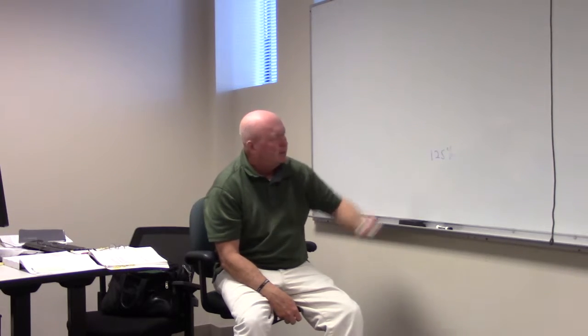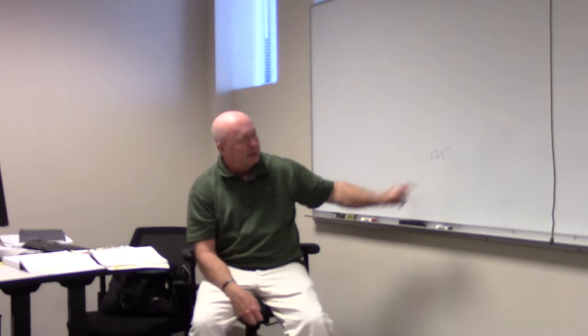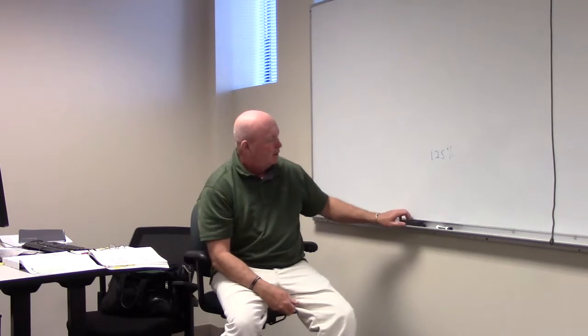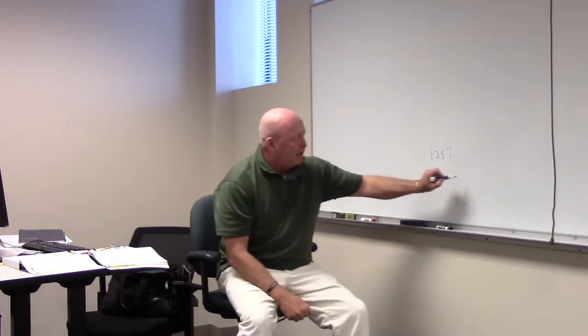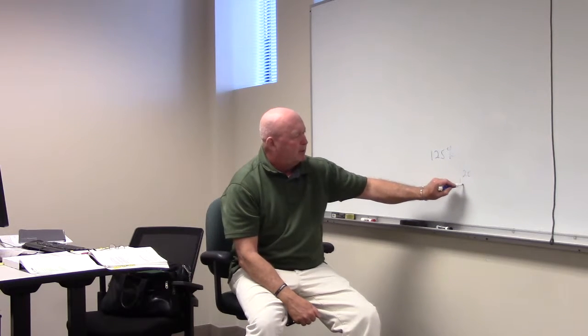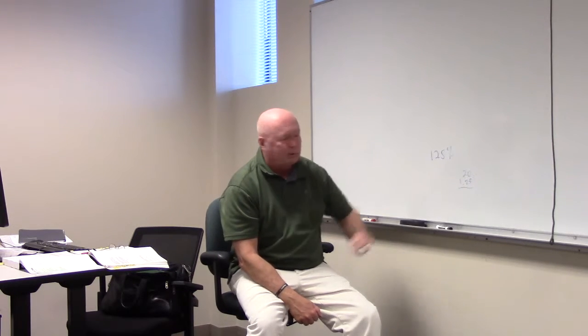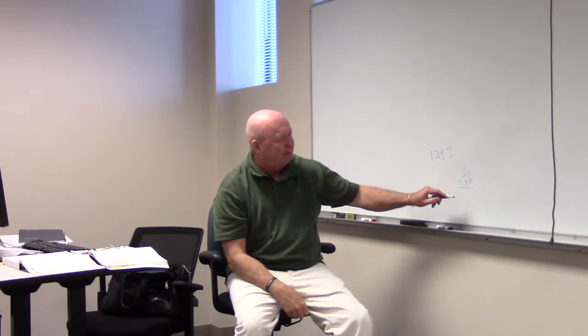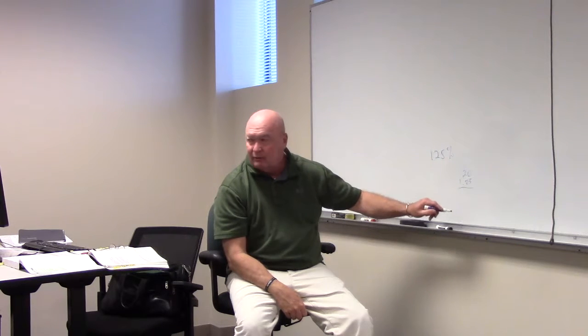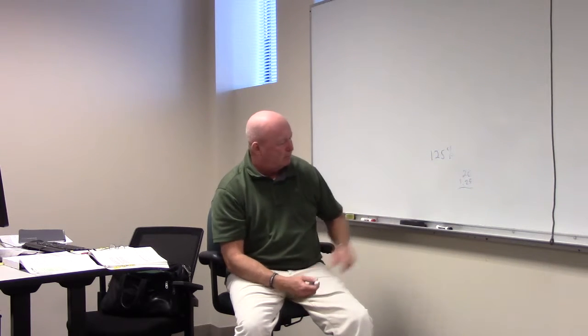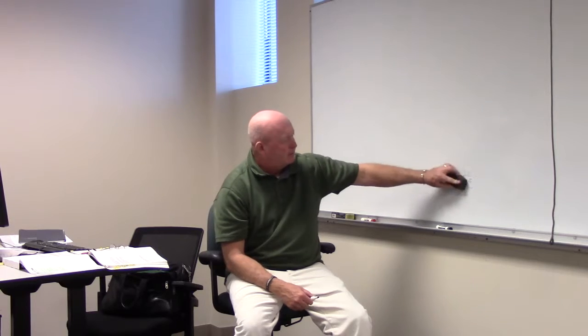125%. Continuous loads. Always remember, continuous is 125%. Okay, so if we had a 20 amp continuous load, it would be what? 20 times 1.25, right? Okay. Or you could take 20 times 0.25 and then add that to the 20, whichever one you want to do. Make sense? Yes, sir. Okay. Reading on.